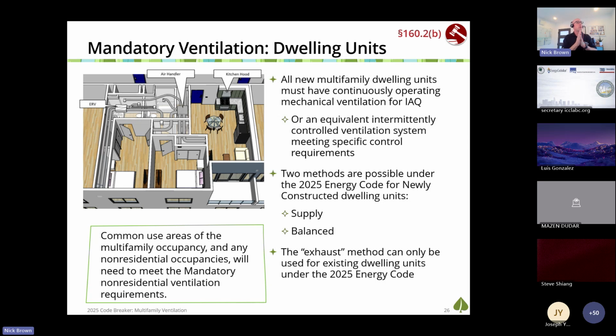All right. So here's section 160, the multifamily chapter. All new multifamily dwelling units must have continuously operating mechanical ventilation for indoor air quality, just like we've always had, or an equivalent intermittently controlled ventilation system meeting specific control requirements. In my experience, it's easier to just put in the continuously operating mechanical ventilation system than to cycle it on and off and prove that it functions equivalently. Although people from other states tend to really like those systems, just not that practical to meet California Energy Code.